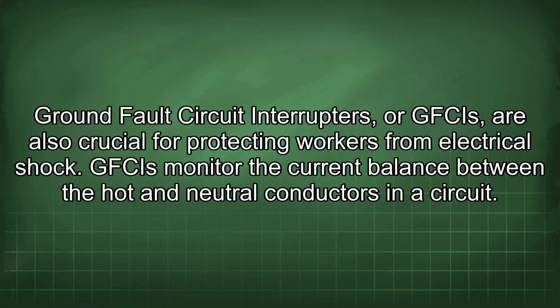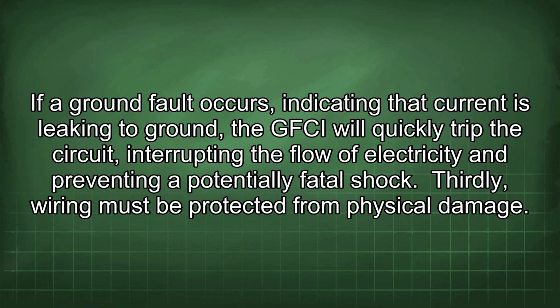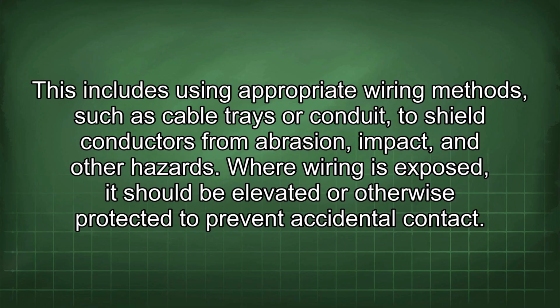Ground fault circuit interrupters, or GFCIs, are also crucial for protecting workers from electrical shock. GFCIs monitor the current balance between the hot and neutral conductors in a circuit. If a ground fault occurs, indicating that current is leaking to ground, the GFCI will quickly trip the circuit, interrupting the flow of electricity and preventing a potentially fatal shock. Thirdly, wiring must be protected from physical damage. This includes using appropriate wiring methods such as cable trays or conduit to shield conductors from abrasion, impact, and other hazards. Where wiring is exposed, it should be elevated or otherwise protected to prevent accidental contact.